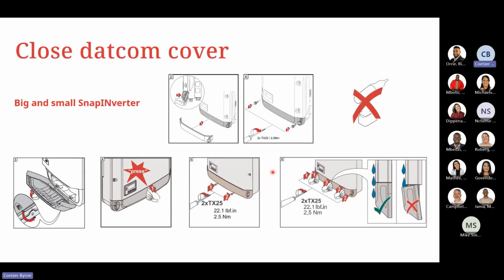Once we've done our AC and DC connection points to the unit and we've reinstalled the inverter, we fasten the two screws that hold the unit to the wall bracket. We then need to close the Datcom cover. On the bigger units and smaller units of the Snap inverter series, you will have a Datcom cover regardless of the size of the unit. The only main difference is that the larger units will have 4 screws that need to be fixed into the inverter, and the smaller units will have simply 2 screws for closing up the Datcom cover itself. Again, we recommend no use of cordless screwdrivers or drills to fasten the screws, as it does bend some of the actual mounting fixture points inside the unit itself.